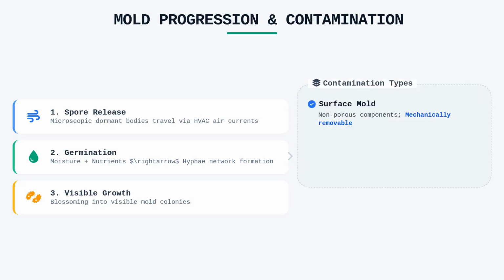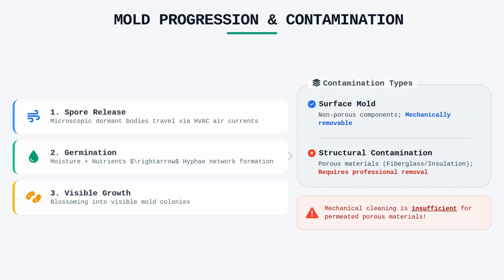It is vital to distinguish between surface mold, which sits atop non-porous components and can be mechanically removed, and deep-seated structural contamination, which penetrates porous materials like fiberglass duct liner or acoustic insulation. Once contamination has permeated the depth of a porous material, mechanical cleaning is often insufficient, necessitating removal or professional remediation to break the cycle of colonization.